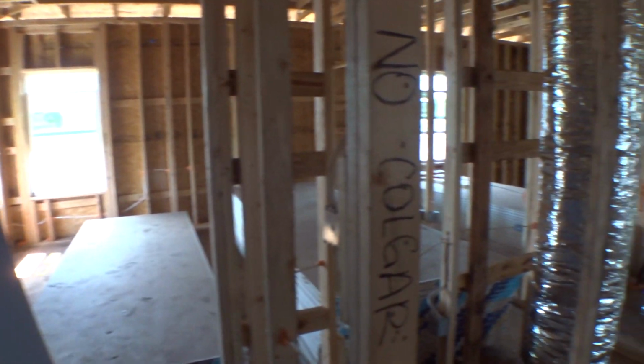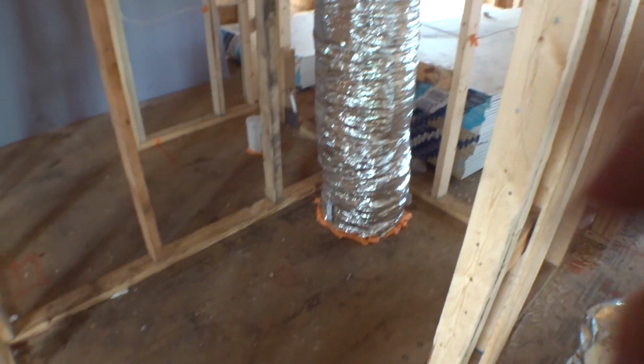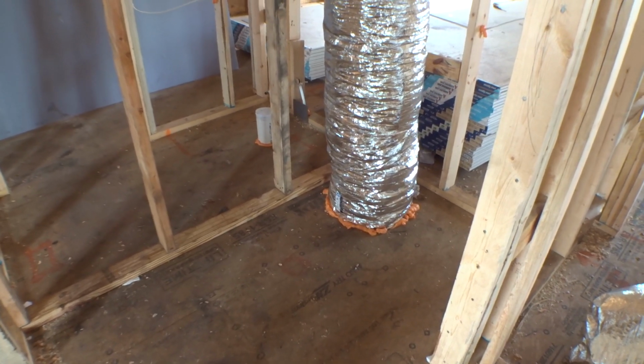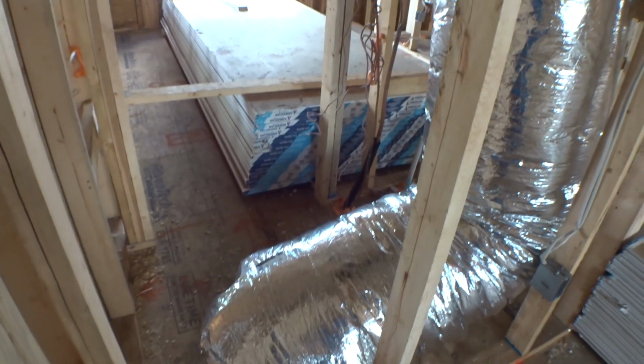So, I think that's a good technical walkthrough. I'm going to actually make it easier on myself and walk through this wall. This is your air handler closet. There's going to be two. Looks like we got our air handler here. We got a closet full of that, and you see how that return goes through the floor, so it's an opening basically, so they have to fire stop that as well. And this of course is where the air handler closet actually is. I apologize for that.